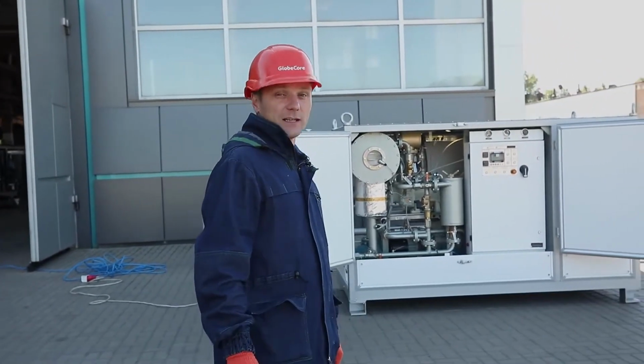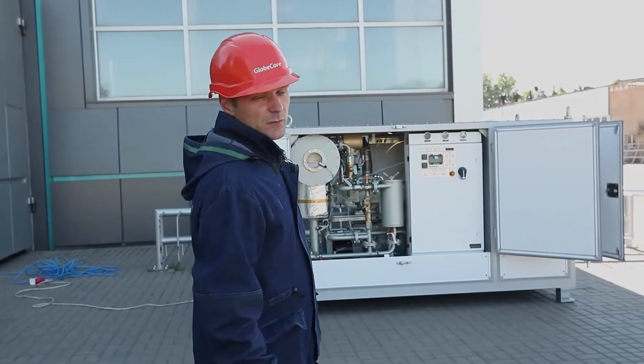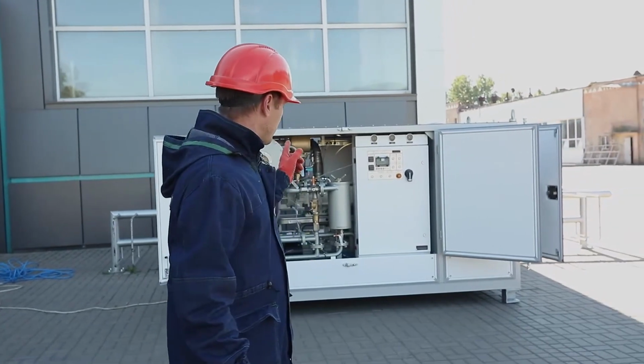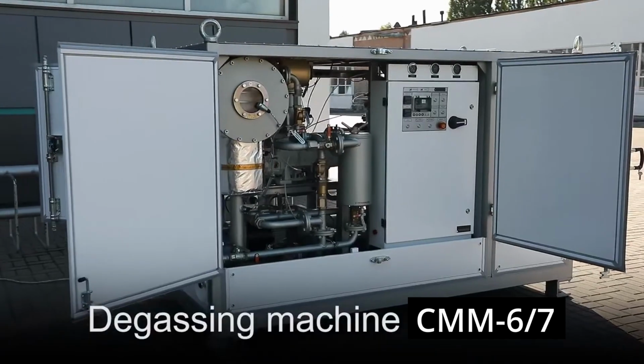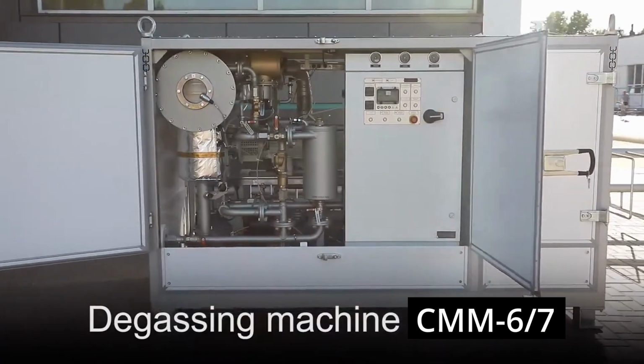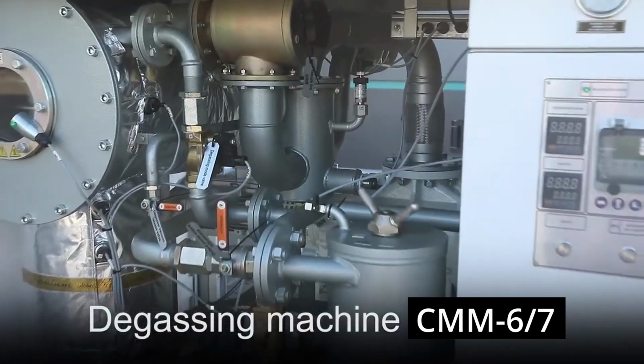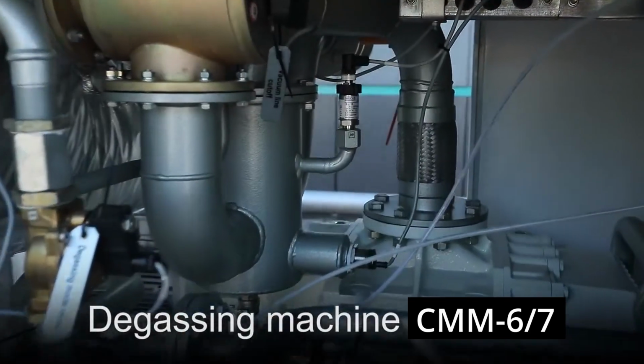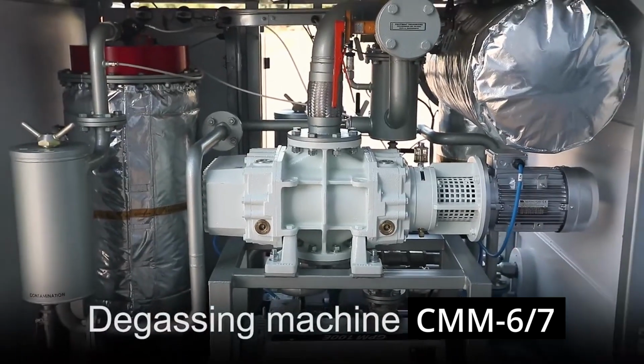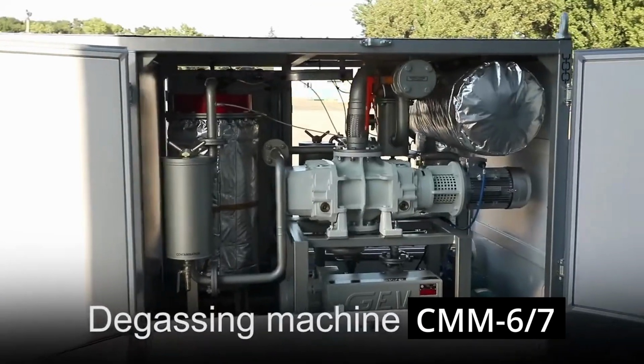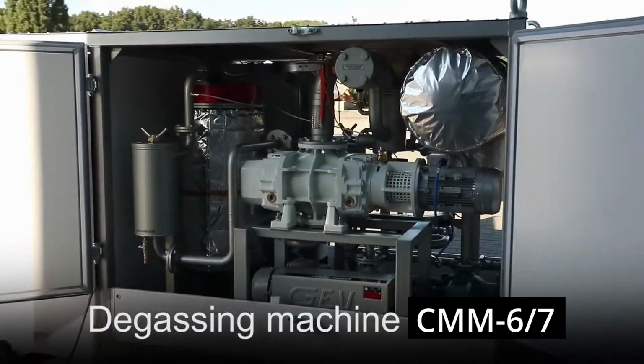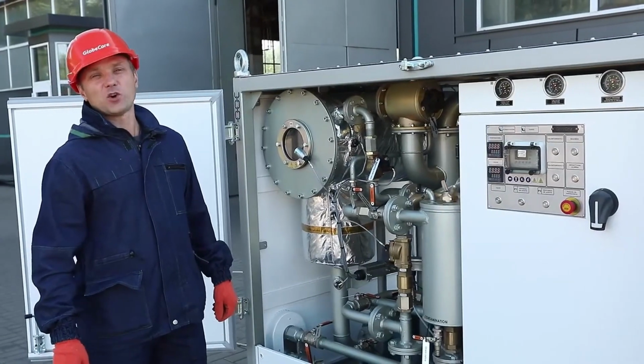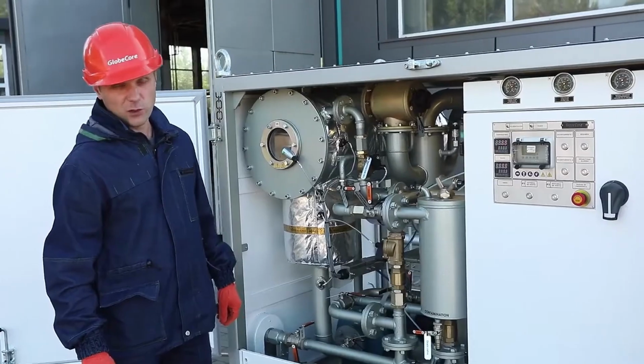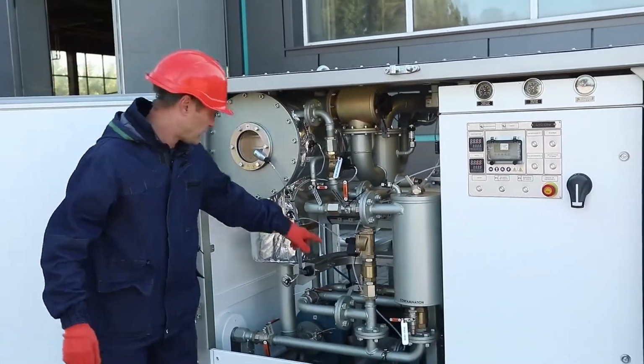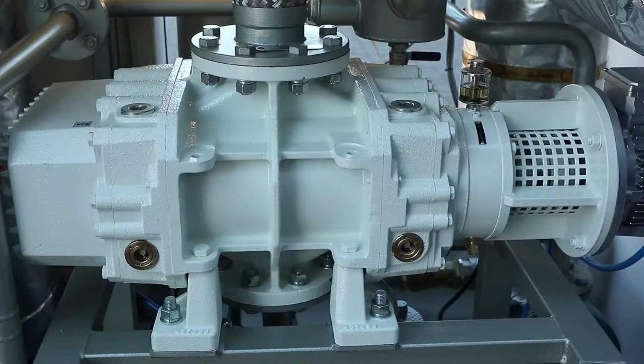Right now, we are going to focus on one of these machines. This is CMM-6/7. Its main difference from low vacuum machines consists in the presence of a two-stage vacuum system, which includes backing and booster pumps that create a high vacuum.